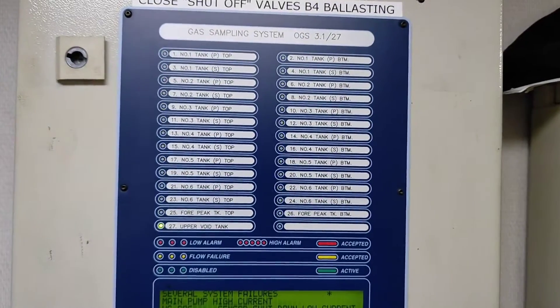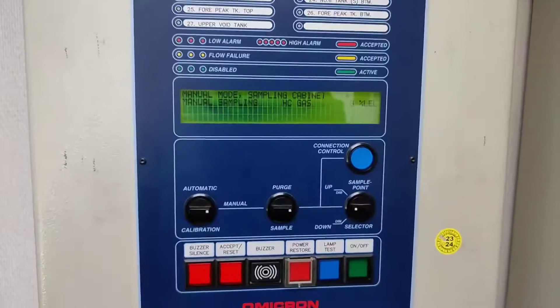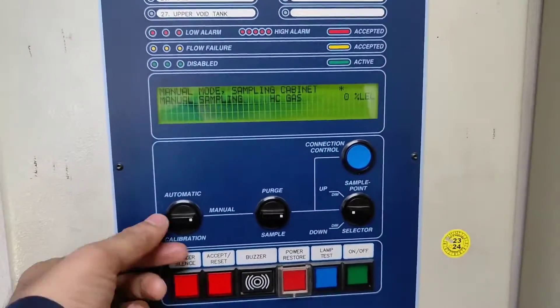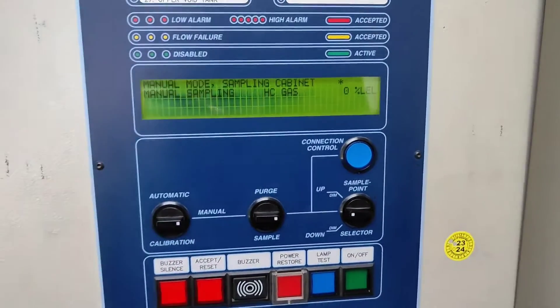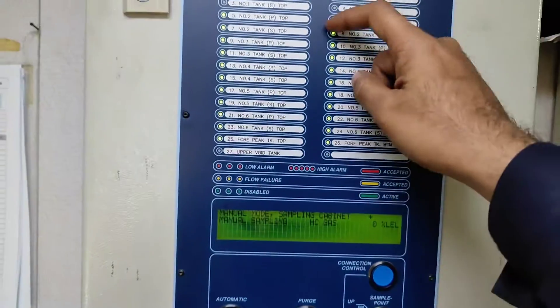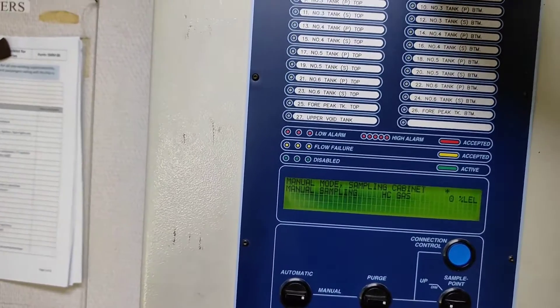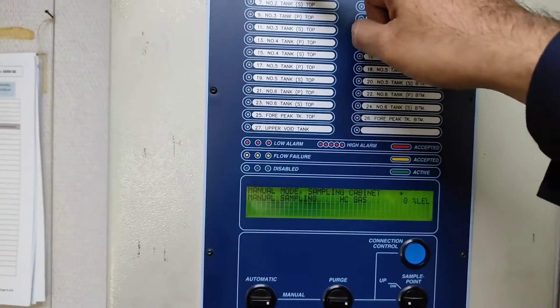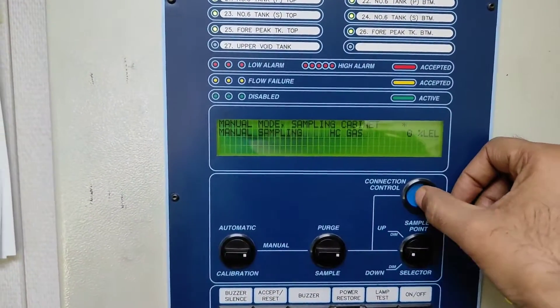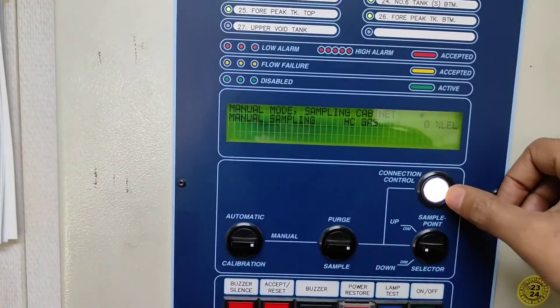The indicator will be flickering because only one sampling point is open. If you want to disconnect or connect any sampling line, you have to put the system in manual mode. Then you turn the selector up and down to choose which channel you want. Right now you can see only number five is not flickering, so number five is selected. If you press the connection control, you can see 'channel disabled in automatic mode' — so number five is now disabled.